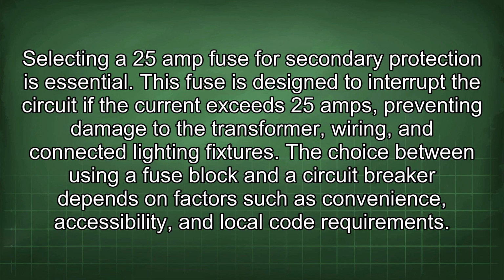This fuse is designed to interrupt the circuit if the current exceeds 25 amps, preventing damage to the transformer, wiring, and connectors of the lighting fixtures. The choice between using a fuse block and a circuit breaker depends on factors such as convenience, accessibility, and local code requirements.